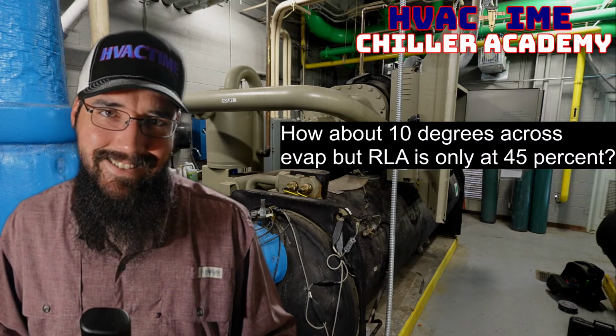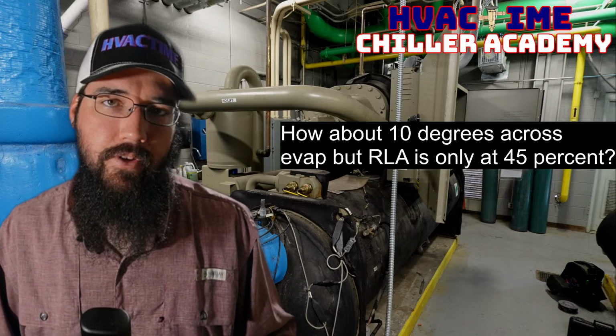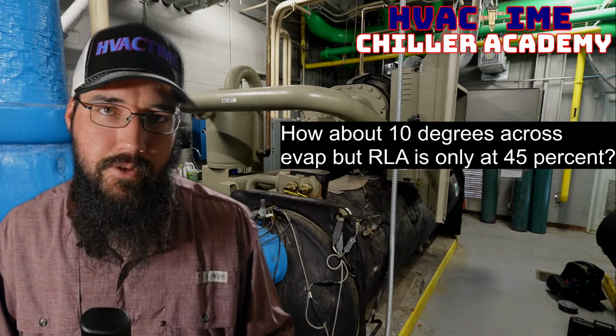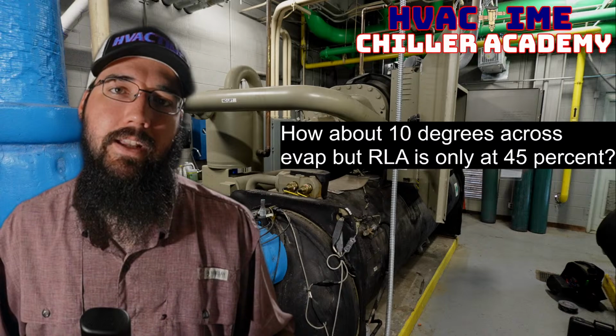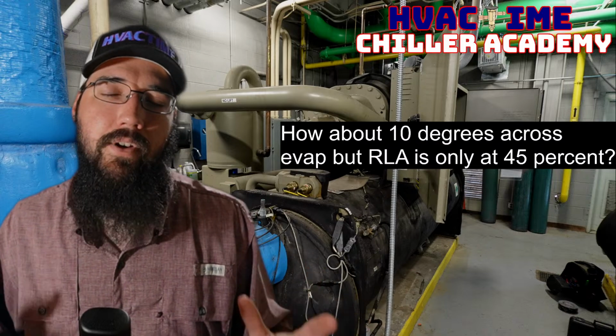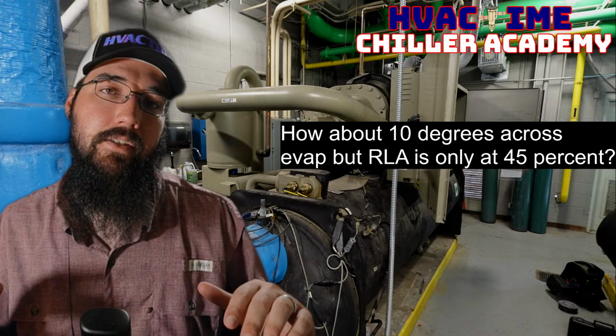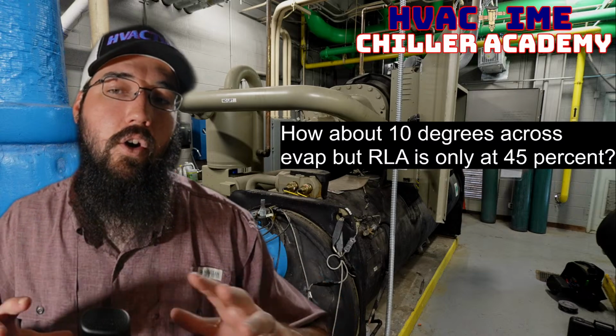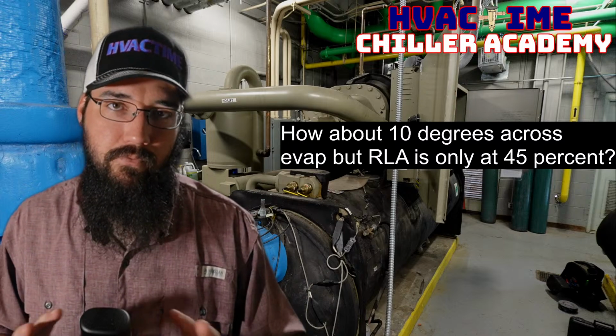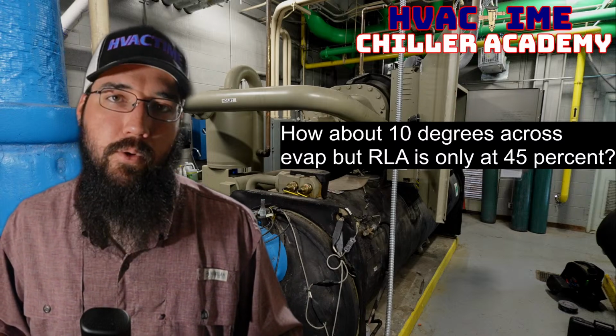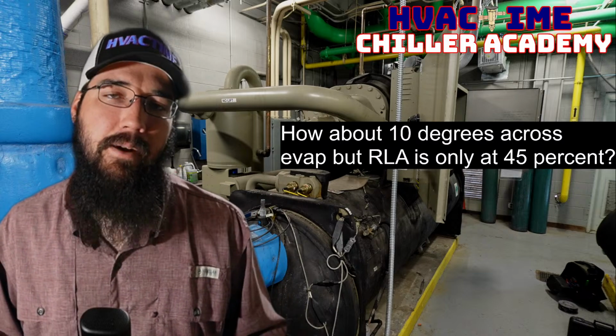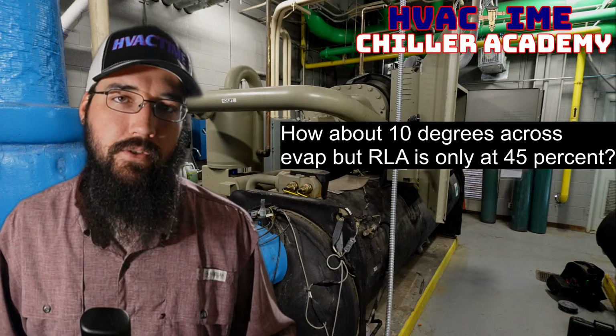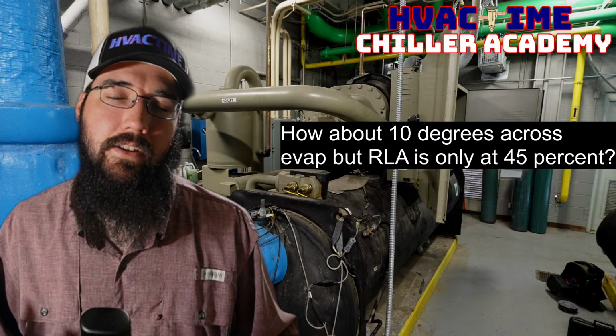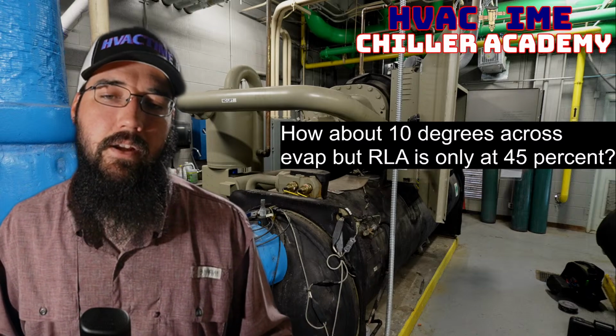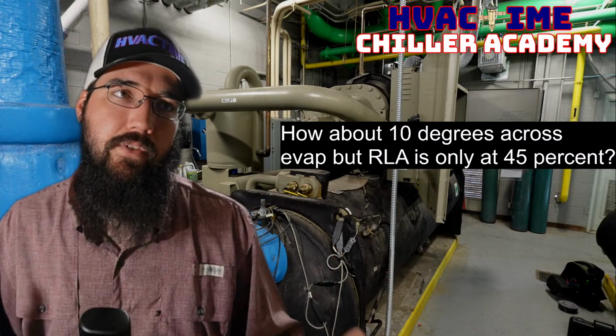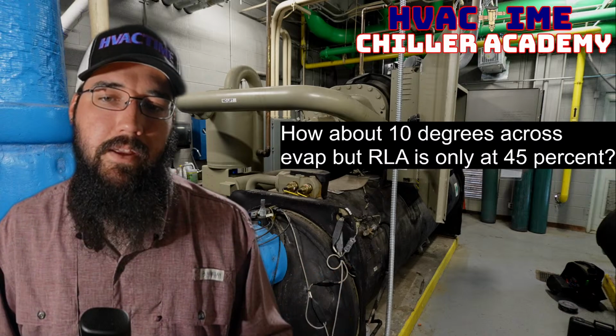Now, that is in the context of knowing for sure that my GPM is correct, my refrigerant charge is good, my tubes are good. That's in the context of all these other variables that impact that differential temperature being in a good condition. It's very, very important. So if we haven't verified that part, then using the temperature difference across there has a lot less value, because if we're flowing too little GPM, that's going to completely change things.